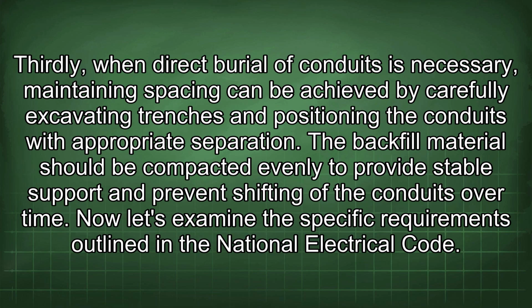Thirdly, when direct burial of conduits is necessary, maintaining spacing can be achieved by carefully excavating trenches and positioning the conduits with appropriate separation. The backfill material should be compacted evenly to provide stable support and prevent shifting of the conduits over time. Now let's examine the specific requirements outlined in the National Electrical Code.